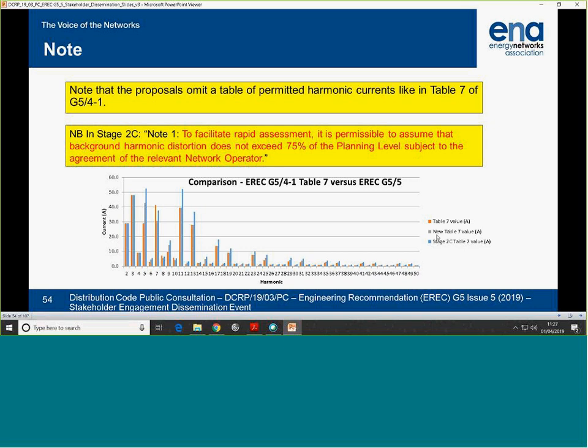But DNOs still want to be able to have values that they can readily reckon, and others as well. So the way around this, we found, was to put a clause in stage 2C, rapid assessments, to assume first of all that the background harmonic distortion does not exceed 75% of the planning level, subject to the agreement of the relevant Network Operator. So, in the graph here, the red or orange values are the old table 7 values in current. The green one, the second one, with grey on it, shows the values of table 7 if you just took account of the new exponent, 0.4 for the fifth, so the fifth has gone up, and the new planning levels.